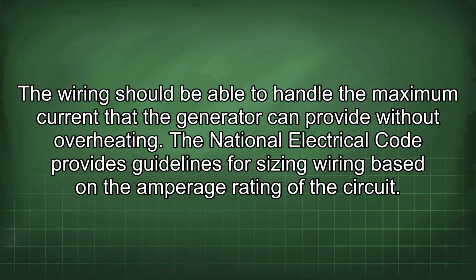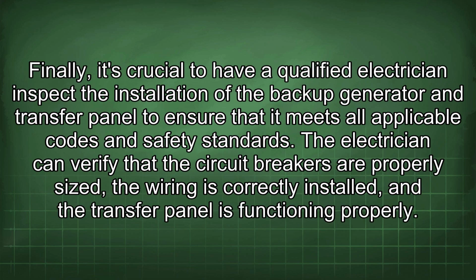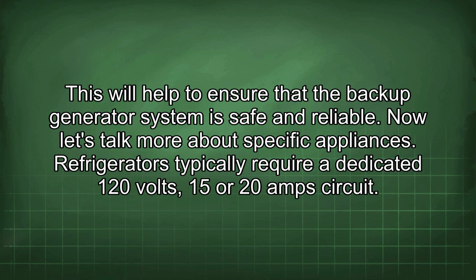The wiring should be able to handle the maximum current that the generator can provide without overheating. The National Electrical Code provides guidelines for sizing wiring based on the amperage rating of the circuit. Finally, it's crucial to have a qualified electrician inspect the installation of the backup generator and transfer panel to ensure that it meets all applicable codes and safety standards. The electrician can verify that the circuit breakers are properly sized, the wiring is correctly installed, and the transfer panel is functioning properly. This will help to ensure that the backup generator system is safe and reliable.